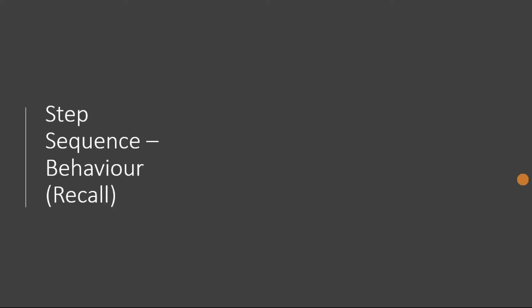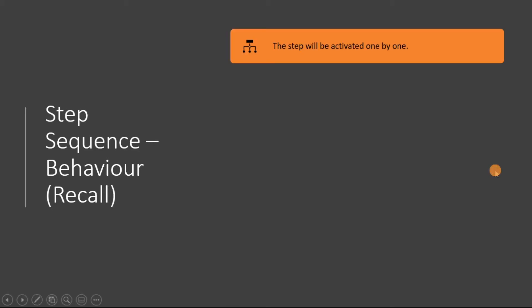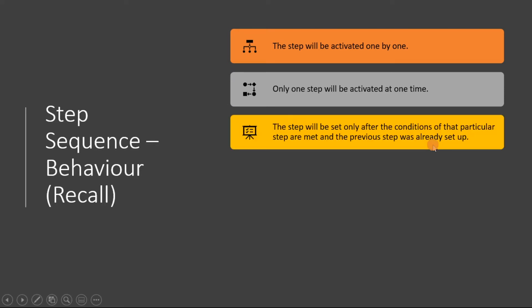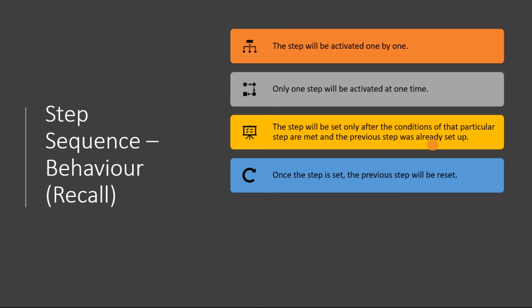To recall, these are the things you need to know in a step sequence. The steps will be activated one by one — it cannot activate two or three steps at one time. Steps will be set only after the conditions for that particular step are met, and the previous process in the previous steps has already been set up.